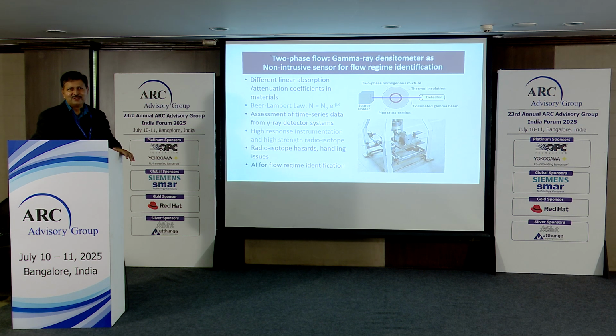Now, the fundamental principle on which the gamma ray or X-ray based systems work is Beer-Lambert's law, that the attenuation of the gamma ray is affected by the presence of the attenuating components inside, that is, in this case, the gas and liquid phases. We could obtain the signature or signals from that and relate it with the pressure signal.